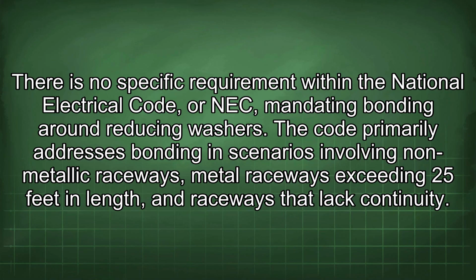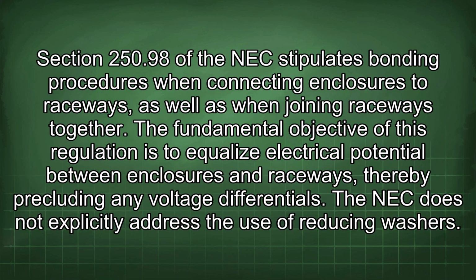There is no specific requirement within the National Electrical Code, or NEC, mandating bonding around reducing washers. The code primarily addresses bonding in scenarios involving non-metallic raceways, metal raceways exceeding 25 feet in length, and raceways that lack continuity. Section 250.98 of the NEC stipulates bonding procedures when connecting enclosures to raceways, as well as when joining raceways together.